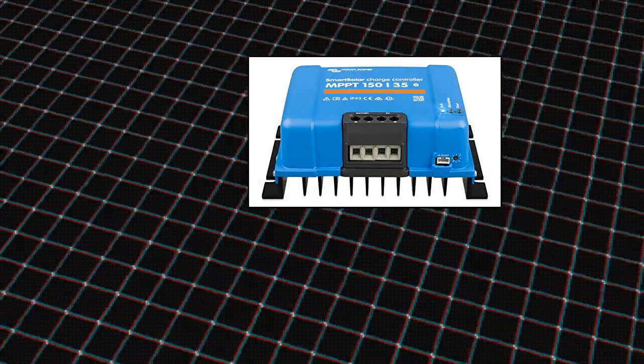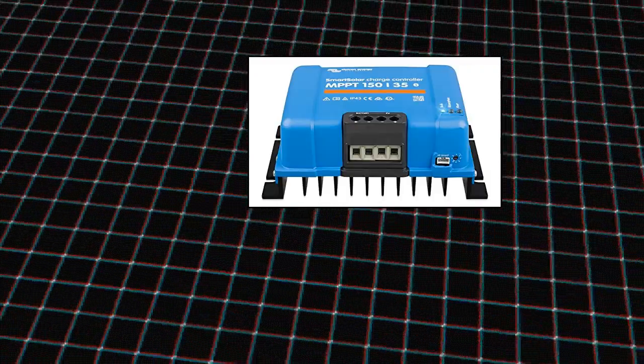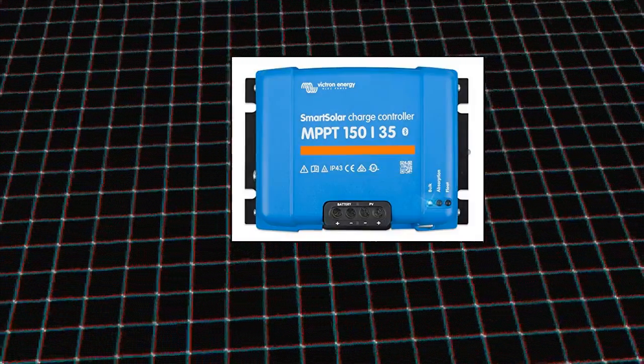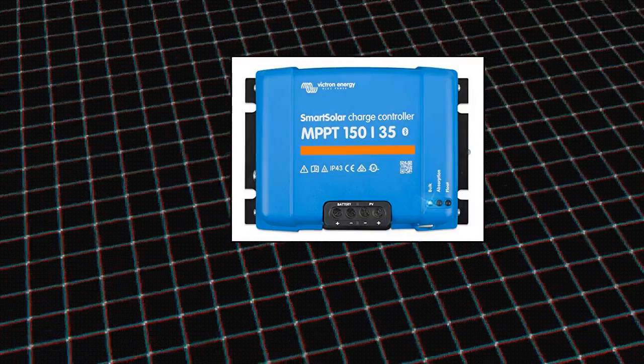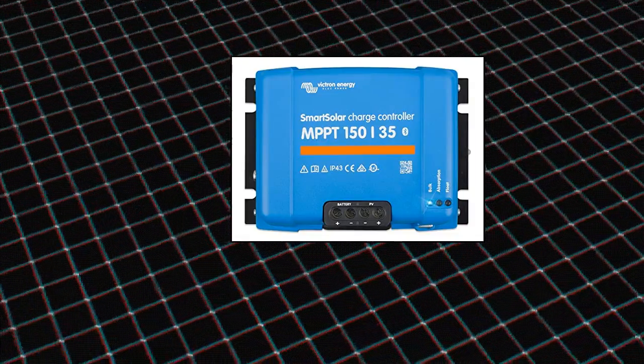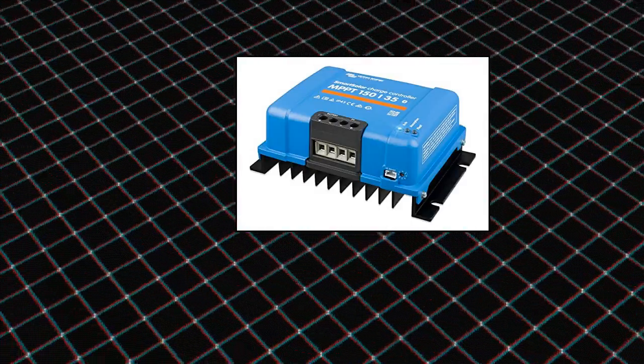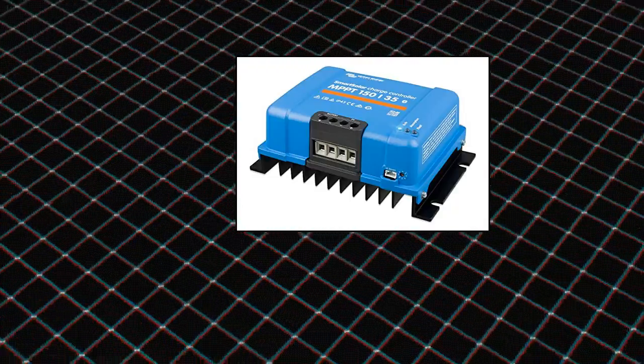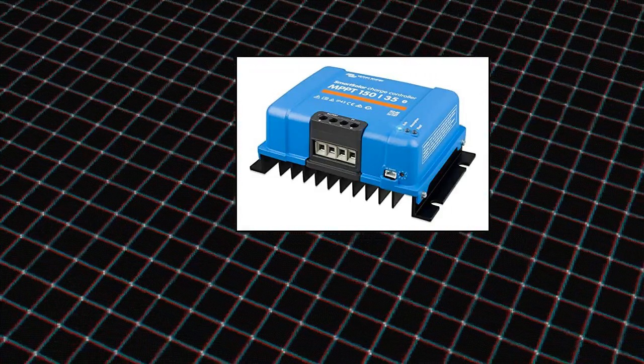It can operate with a battery voltage as low as 0 volts, provided the cells are not permanently sulfated or otherwise damaged. By constantly monitoring the voltage and current output of your solar PV panels, MPPT technology ensures that every drop of available power is wrung out of your panels and harvested for storage.